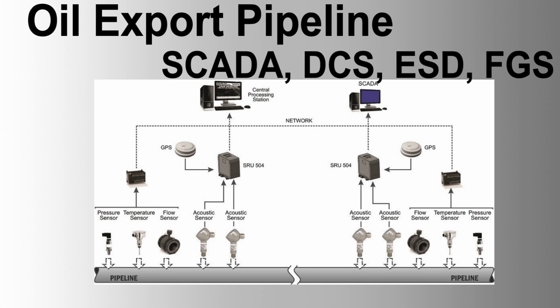Workstations: operator workstations with dual monitors, Intel Core i7 processors, 16 GB RAM and SSD storage. Networking: redundant 10/100/1000 Base-T Ethernet LAN with fiber optic backbone for long-distance communication. Communication protocols: Modbus TCP/IP, OPC UA, DNP3, IEC 60870-5-104. Software specifications: SCADA software, Rockwell Automation FactoryTalk View SE.